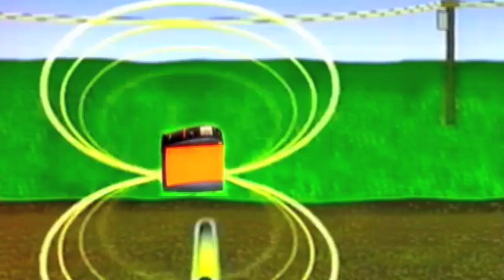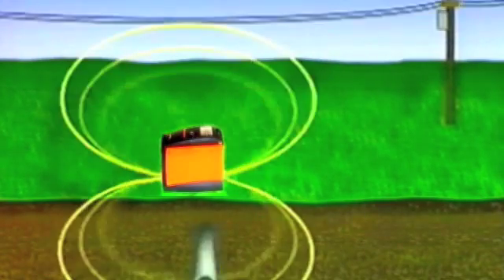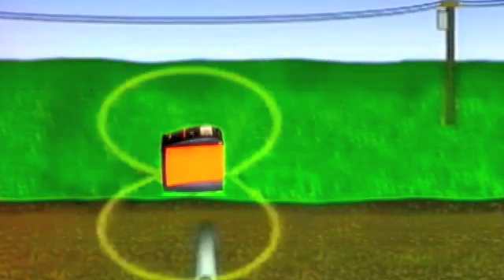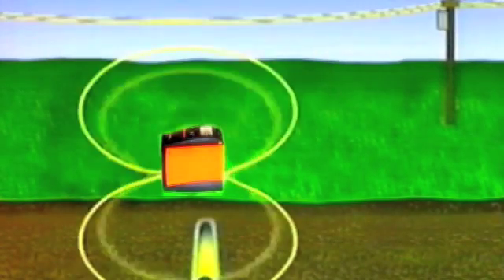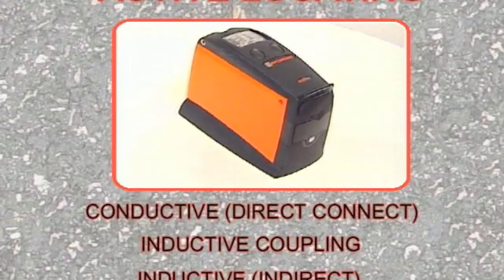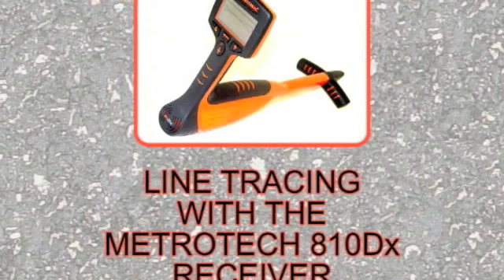When you are locating in the inductive mode, remember that it is very easy to interpret signals induced onto other conductors, especially overhead power lines, as coming from your target conductor. After having set up the transmitter in the locating mode best suited for your job, you are ready to trace the line with the Metrotech 810Dx receiver.